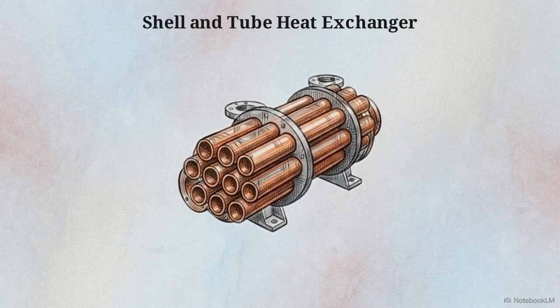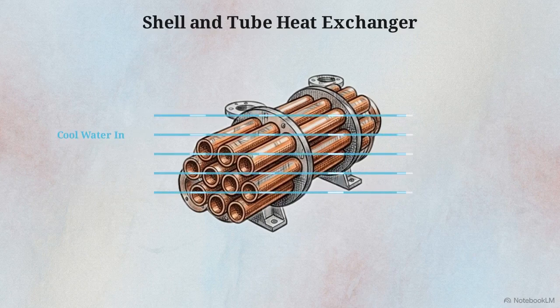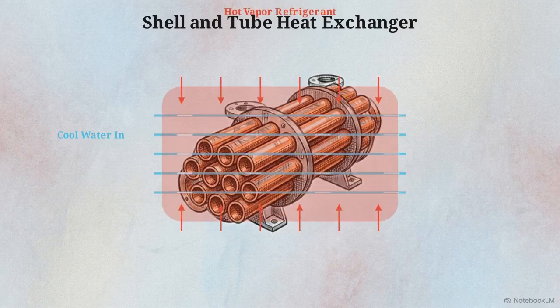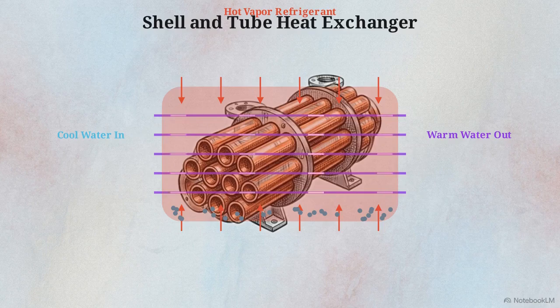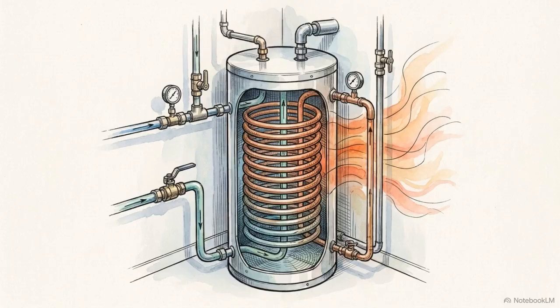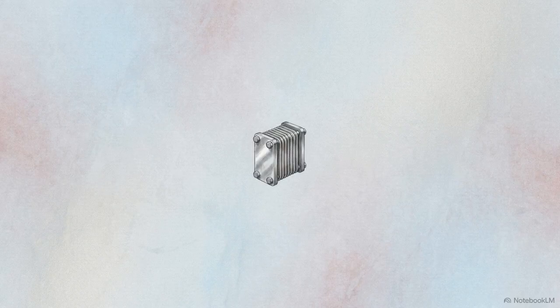This diagram outlines the shell and tube architecture, the backbone of industrial water chillers. Cold water flows continuously through the internal tubes, while hot vapor refrigerant floods the surrounding outer shell cavity, transferring its heat into the water. For medium capacities, where a smaller footprint is needed, scaled-down variants like shell and coil or double-pipe condensers offer similar liquid-to-liquid heat exchange while being easier to clean. In modern, highly compact applications, we use plate condensers.